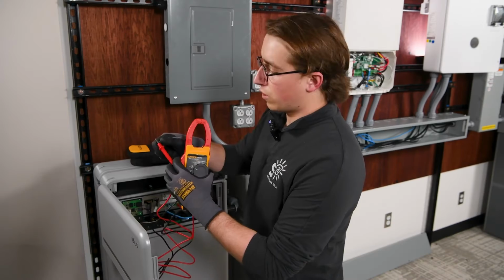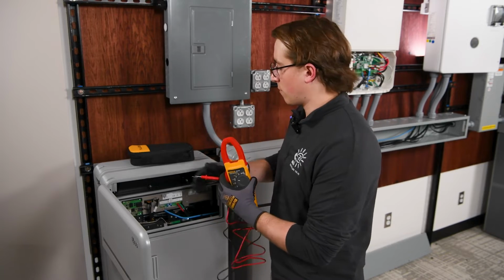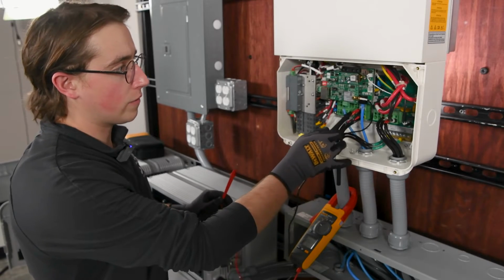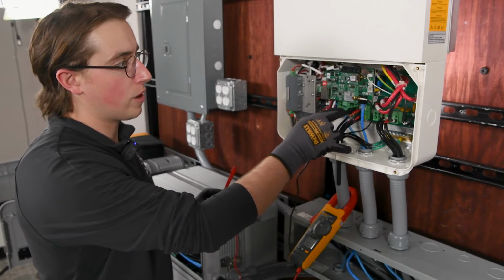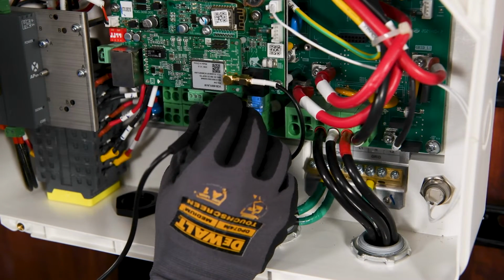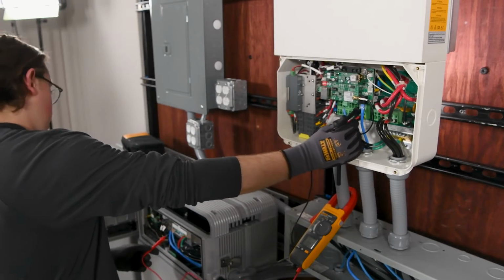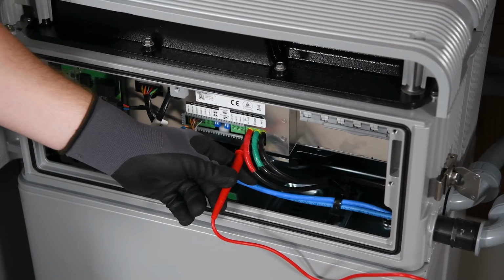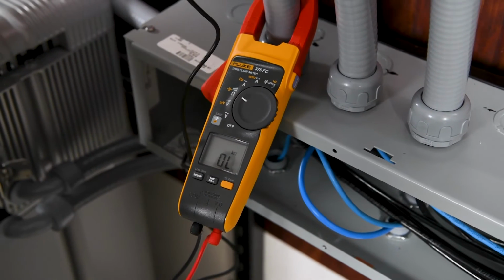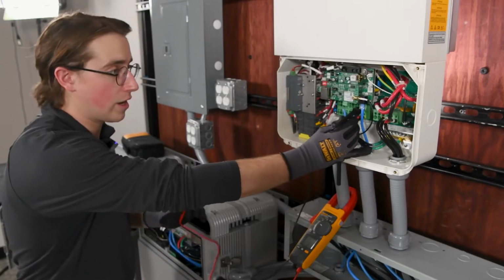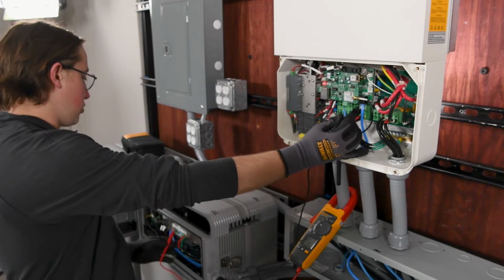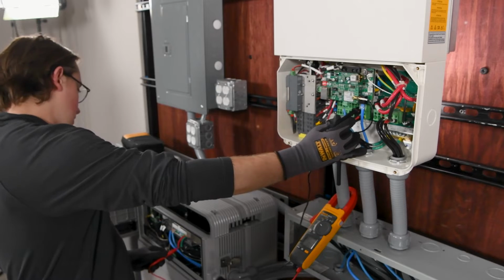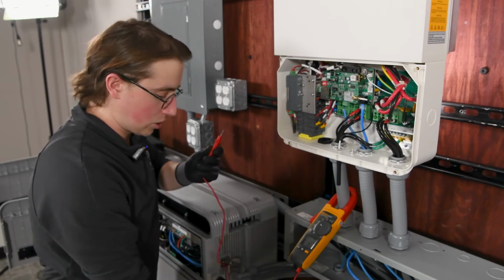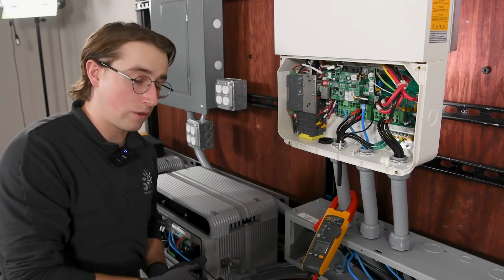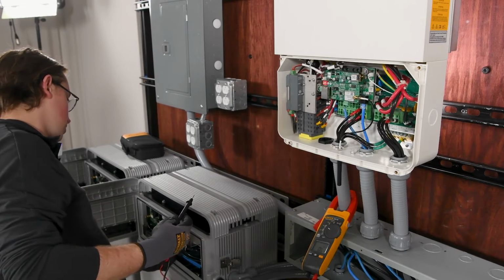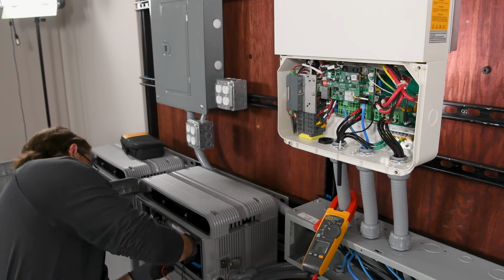We'll make sure that we're getting a good signal, and then we'll do our continuity test between the battery and the inverter. One probe will go to the inverter. We can use a little square terminal right above the positive input, and all we're doing is touching that back terminal there. We'll take our red probe here and touch it on the bottom square hole on the battery. And as we can hear, we're getting continuity between our 2 positive connection points from our LG Prime battery to our Growatt inverter. And next, just to make sure that we're not getting any solid continuity between positive and negative of our battery terminals, we'll do the same test on the positive and negative inputs.